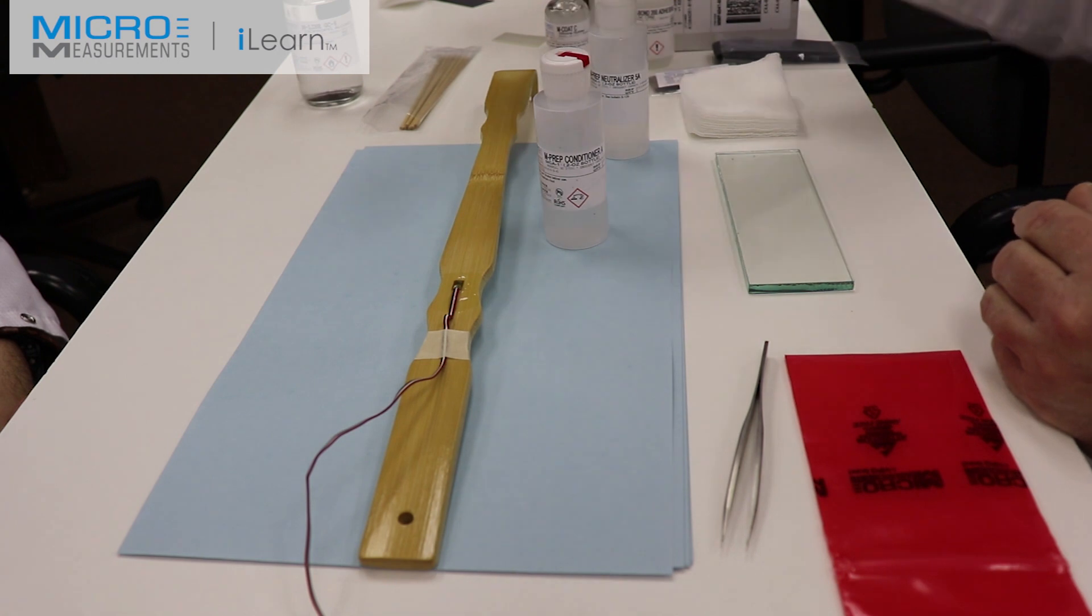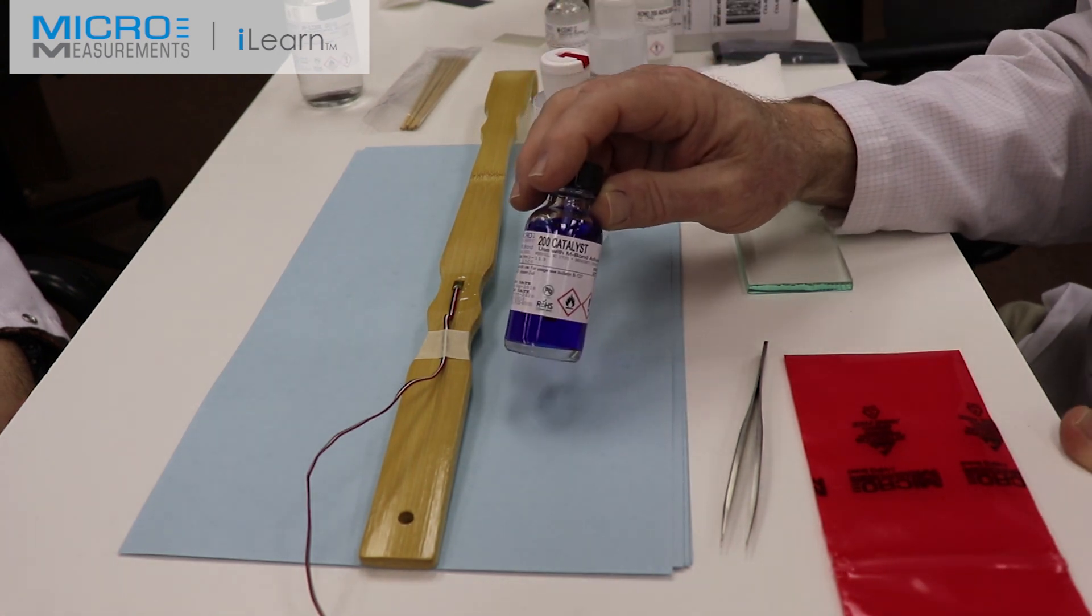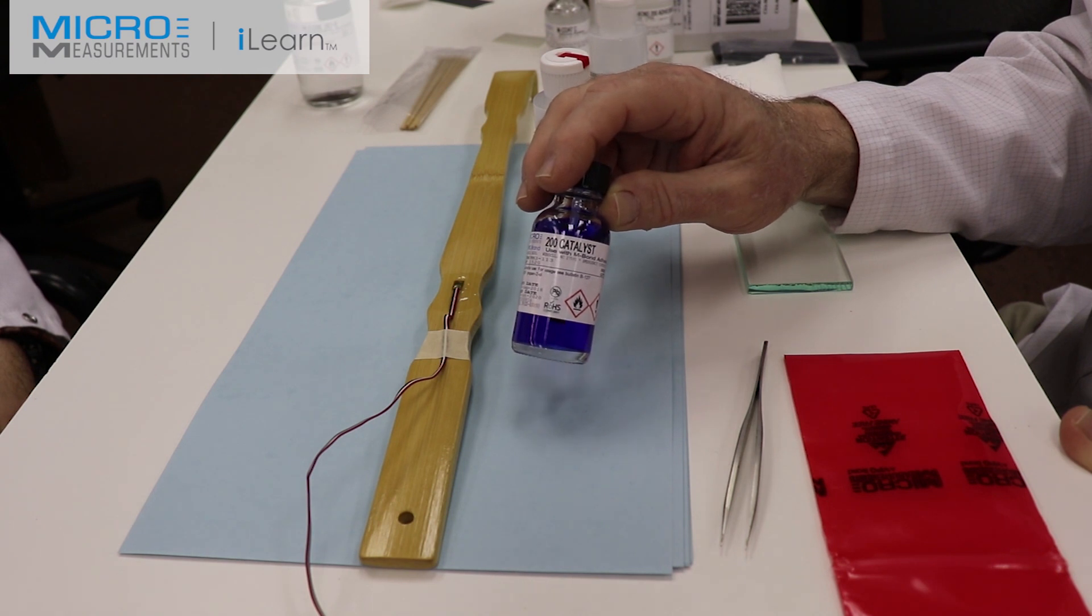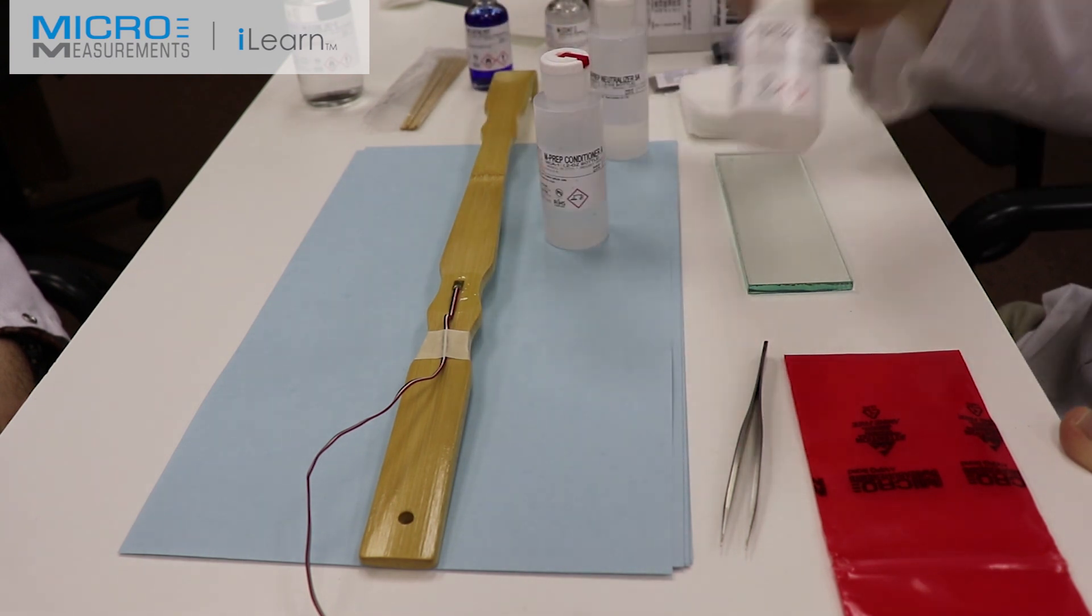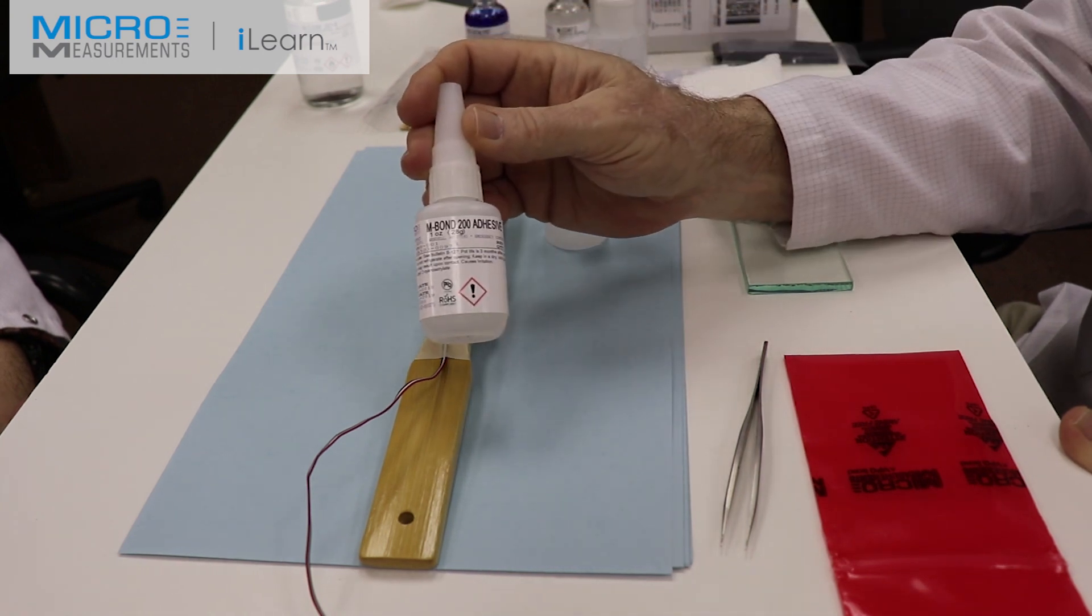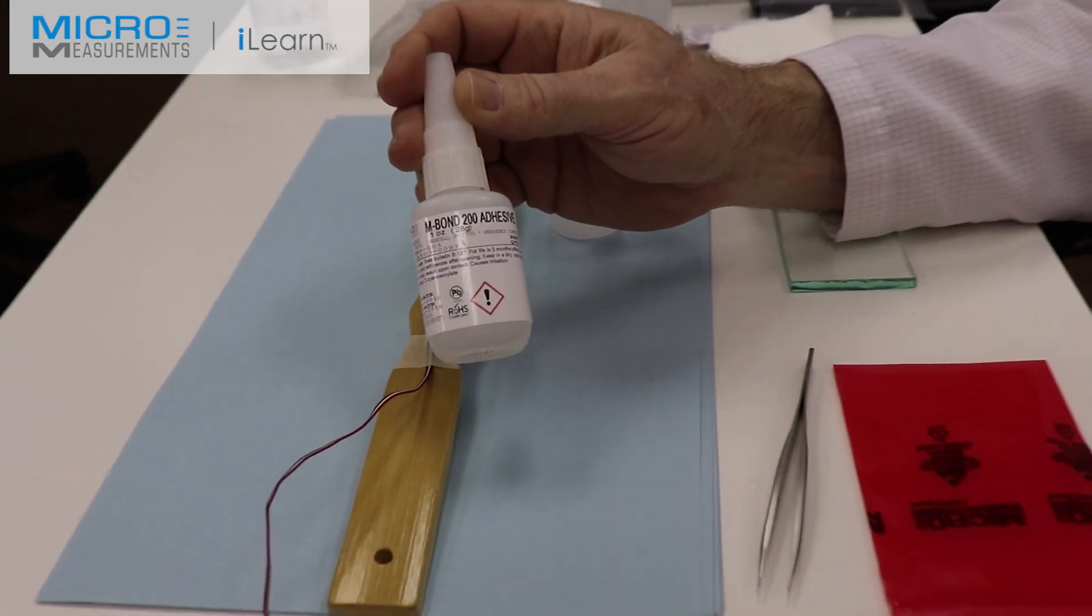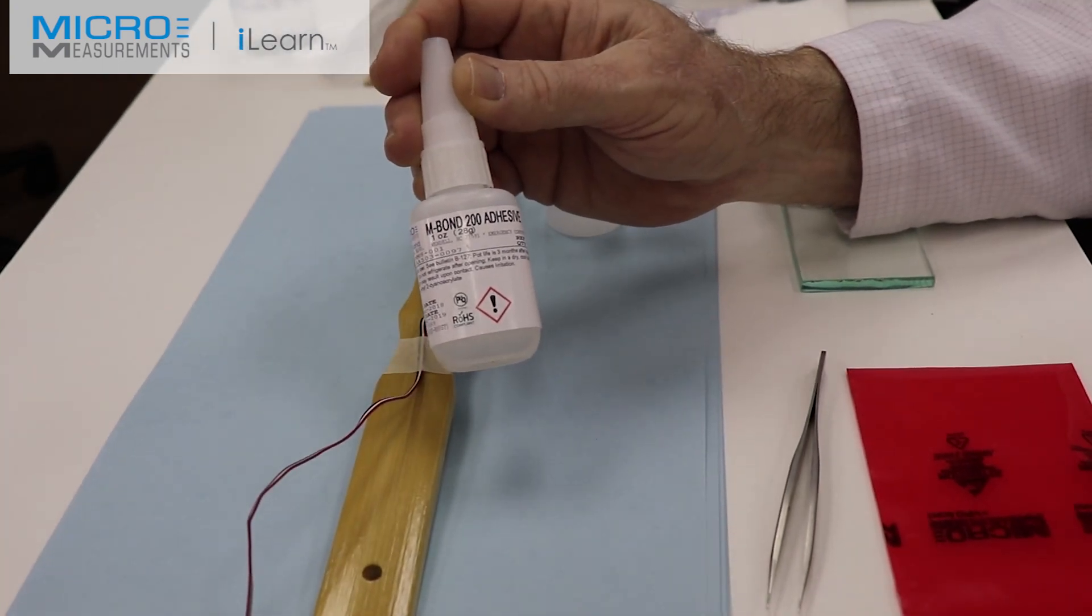The Catalyst-C, to call it a catalyst is really a misnomer, it's more of a controlling agent, was applied to the backing of the gauge and allowed to air dry for one full minute. Then the final step before bonding the gauge was the M-Bond 200, a cyanoacrylate adhesive, instant setting, fairly popular for general purpose stress analysis work.